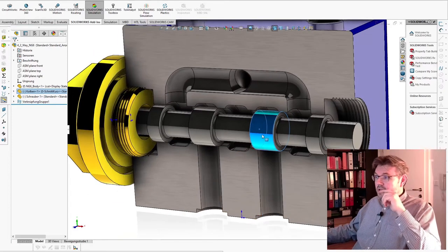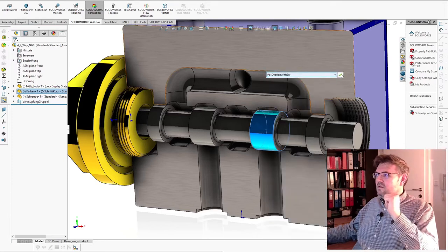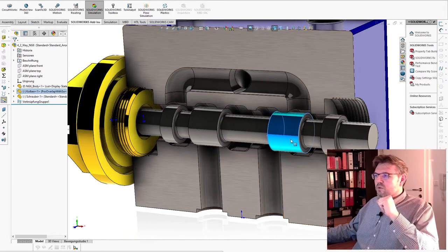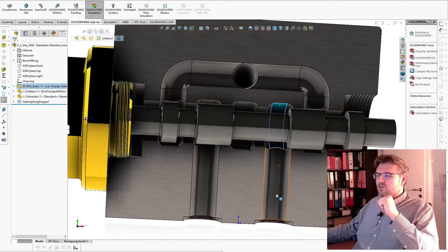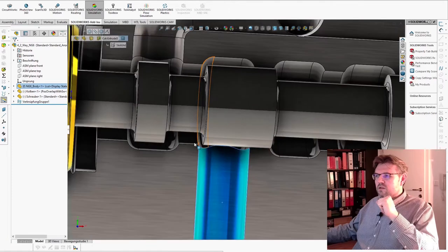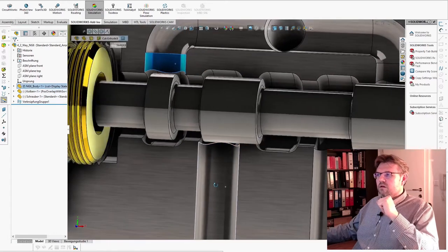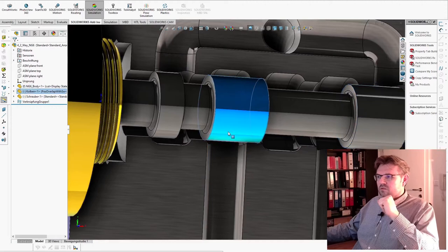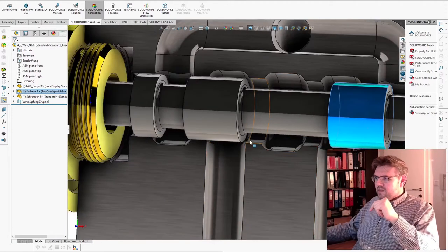And also here, if I just select a different piston inside, a different piston form, then this would be one direction. Now the pressure is connected to this line, a little bit further maybe. This line is connected here to the tank line. Now if I switch, first the tank line is cut off, and then the pressure line is already open.